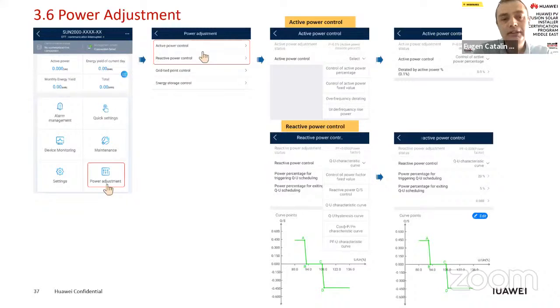After we install the inverter, we have some power adjustments that we can do directly on the inverter. Here we have two options to control the power. One option is directly on the inverter. We have reactive control and active control. For example, for active power control, I can set on the inverter a fixed value or a percentage. In reactive power, I can set a Q characteristic curve. In residential areas, this function is used to keep the inverter running when the voltage is very high. So these are the controls set directly on the inverter.